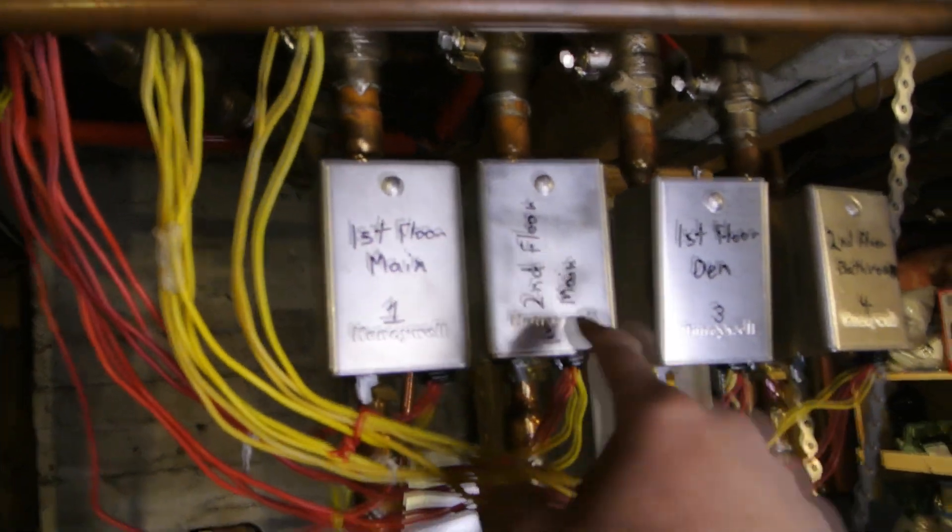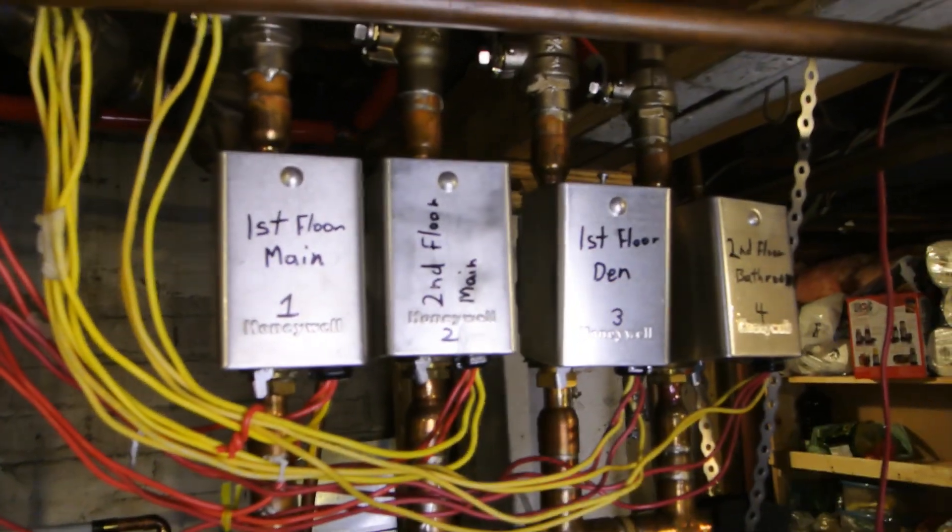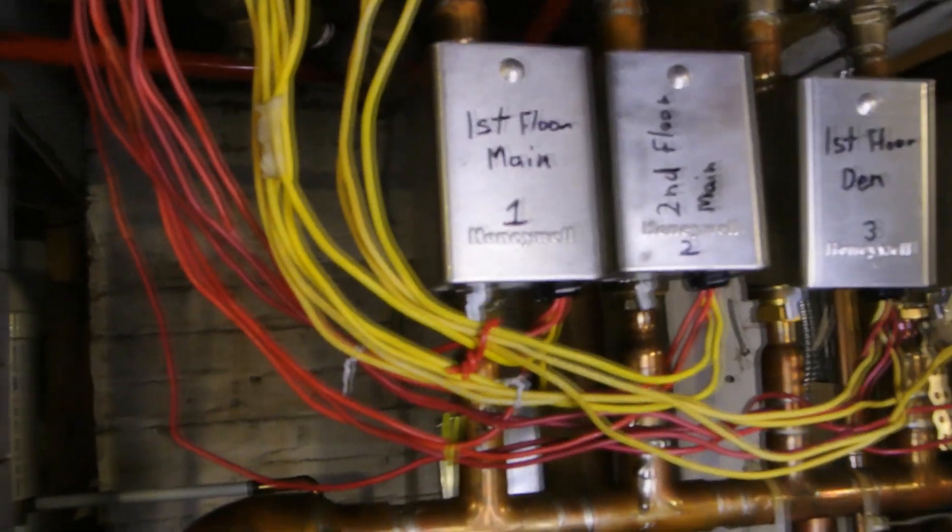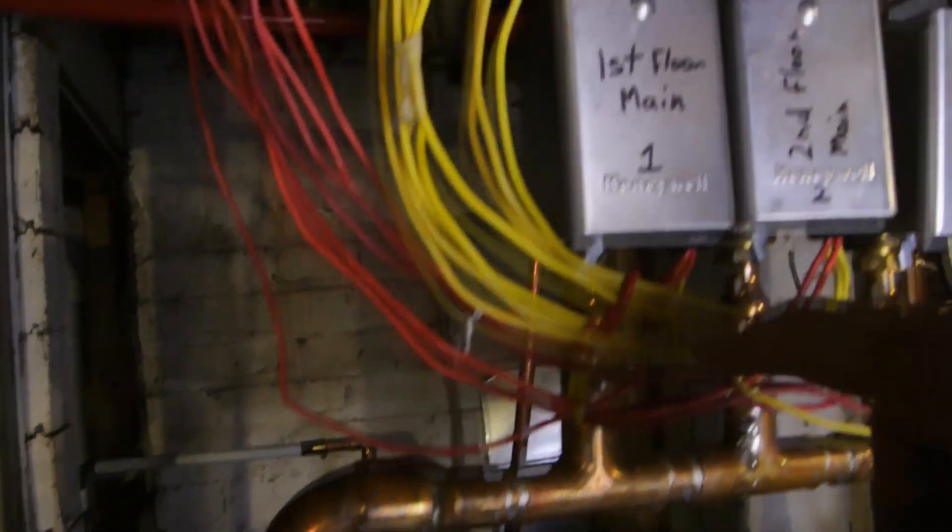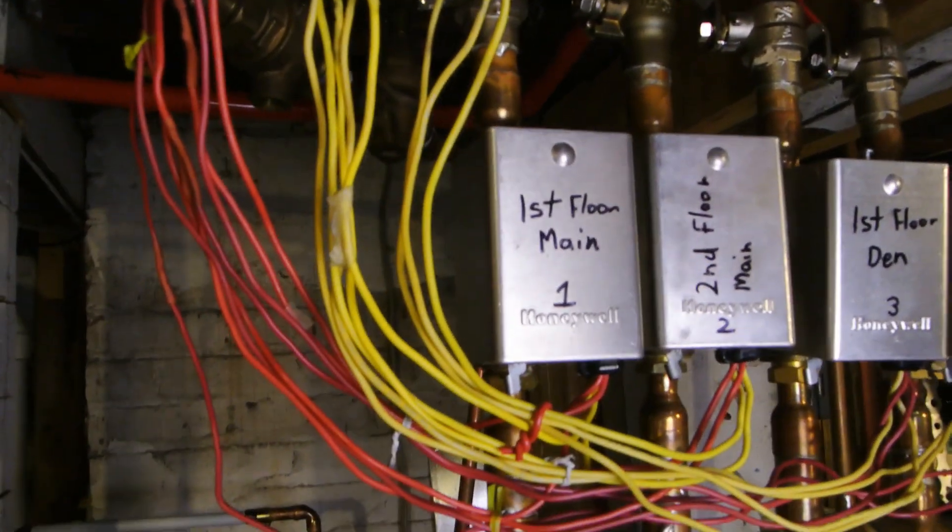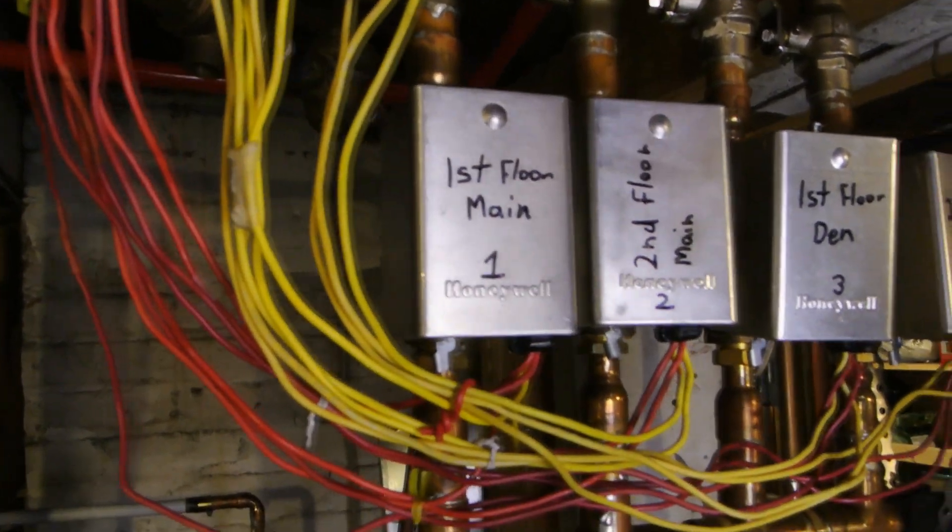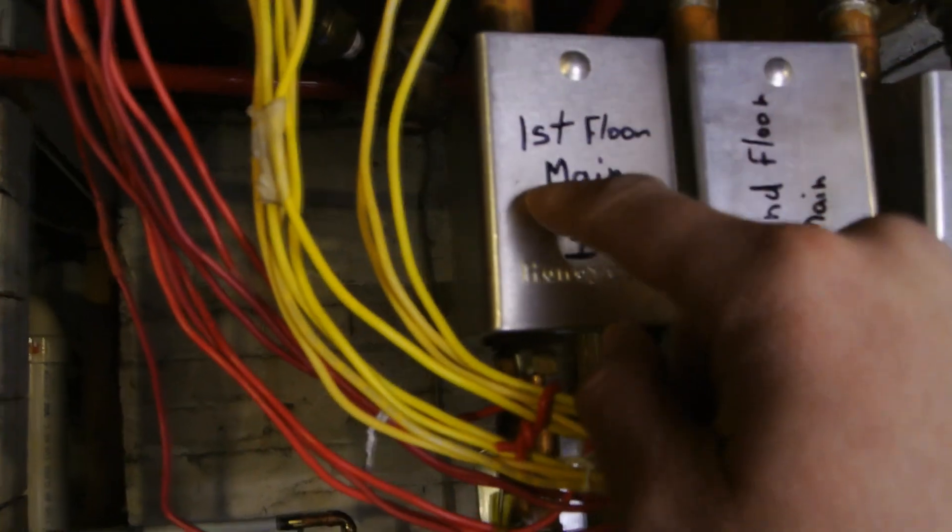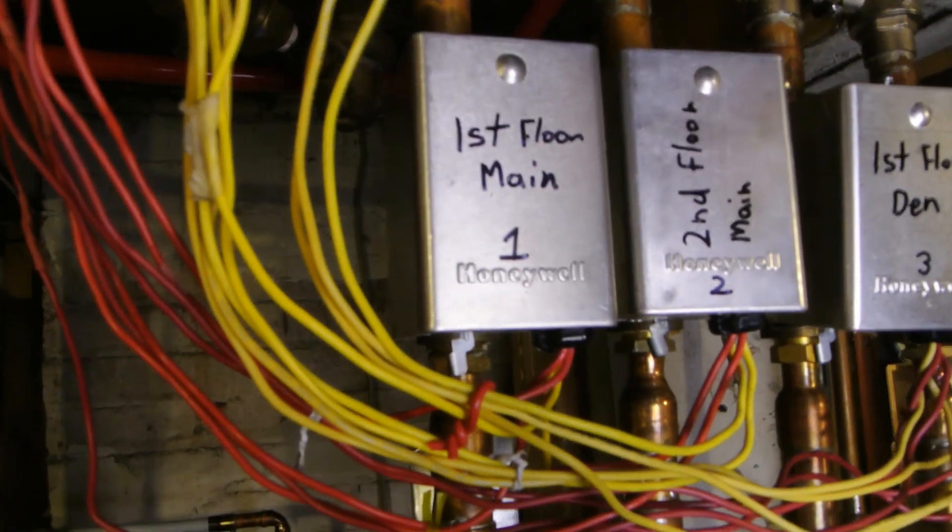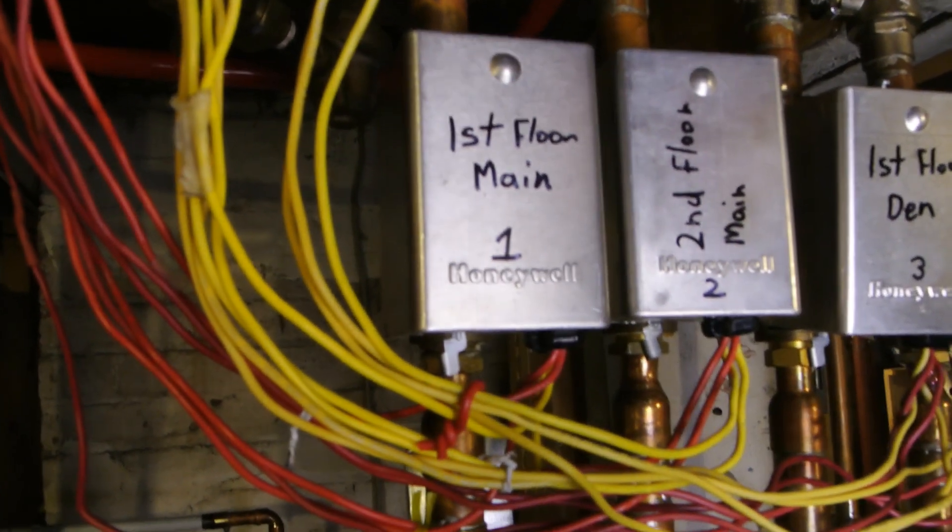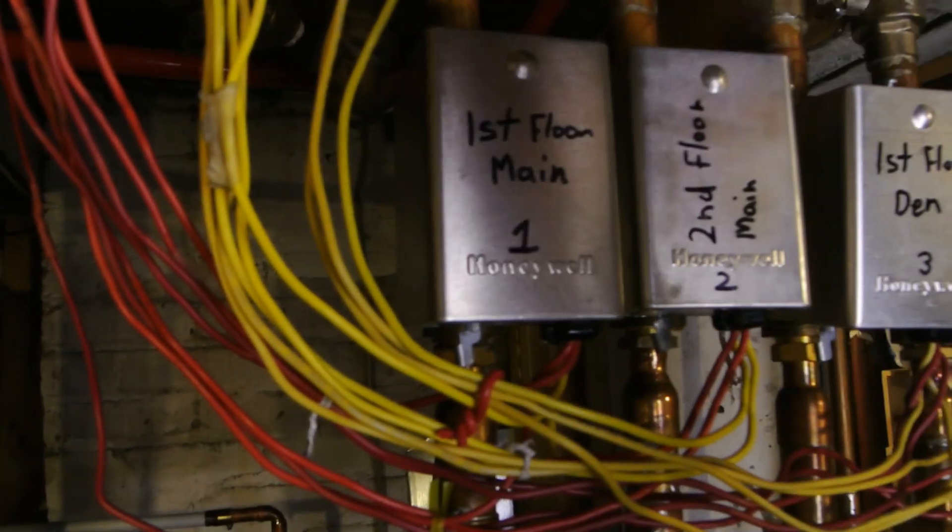You can see mine has main, second floor, the den, the bathroom - so I have four zones. Hot water flows from the boiler through the valve if it's open and circulates around the house, then back to the boiler and gets reheated. That's the cycle of heating. Real simple: when you turn on the thermostat, it completes a circuit and turns on the valve, which then allows hot water to circulate through.